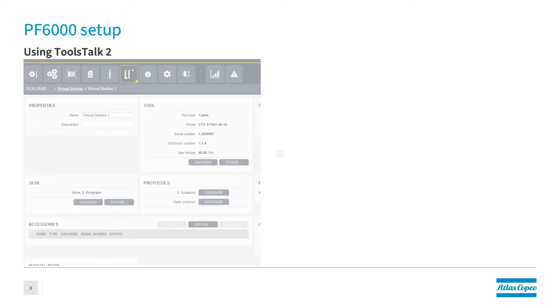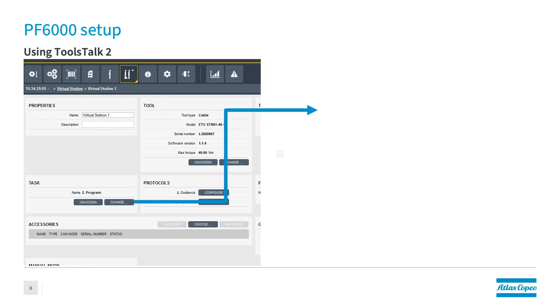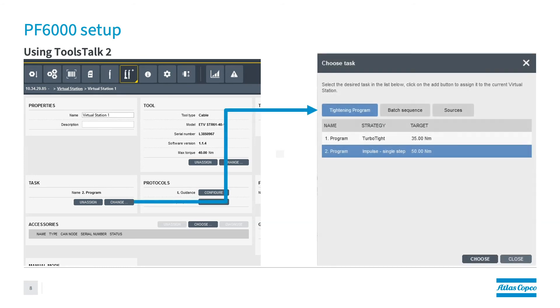Now, in the case of using Tools Talk 2, you're going to go into Tools Talk 2, the virtual station, you're going to go to protocols, open protocol, and then you're going to configure it in Tools Talk 2. Once you do that, you're going to go to the tasks, hit change. Once that opens up, then you're going to go into the tightening program and select the tightening program that you want to run.